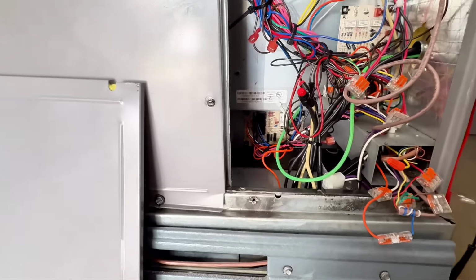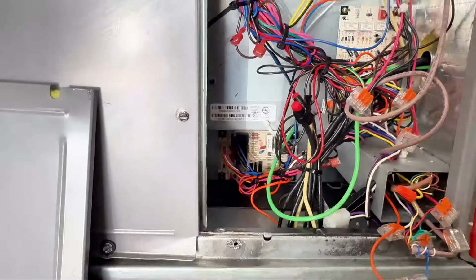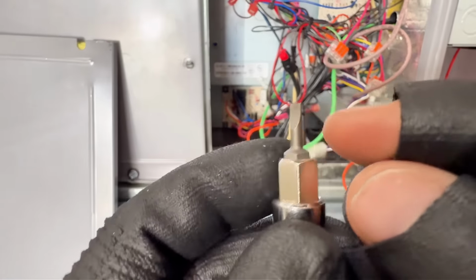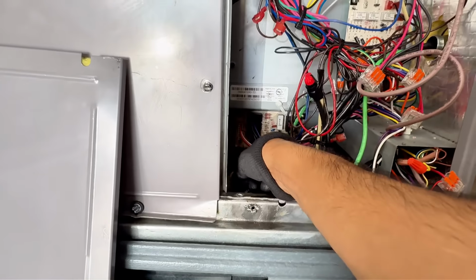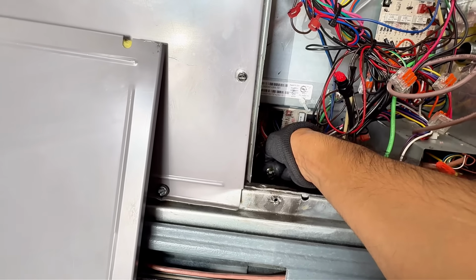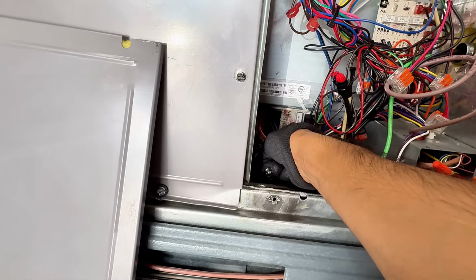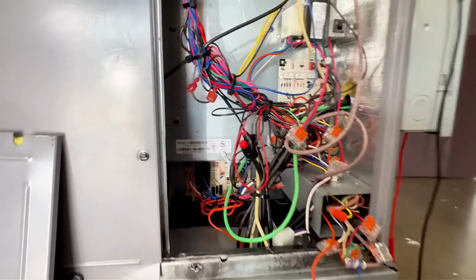So if you see back there, you might not be able to see. You see that harness plug? Right underneath that, there's 2 little pins. Right there. You see the 2 little pins? That's called speed up. So if you want to bypass the 5-minute delay, just get a little part like this and short them to each other. And that should turn it on. So I'm going to go ahead and see what happens when I do that to see if it turns on. Okay. So I did hear the reversing valve click, but my compressor didn't turn on. I can't hear it. So I am going to connect my gauges right now.